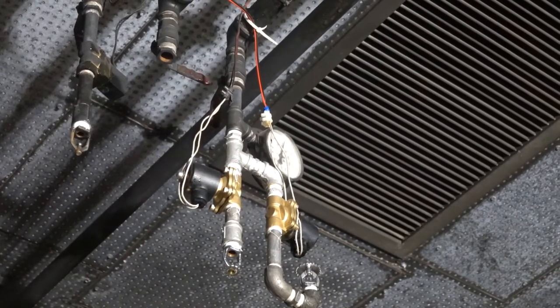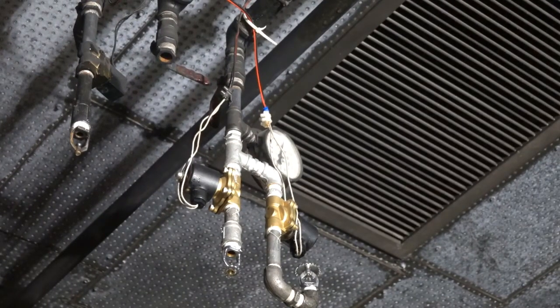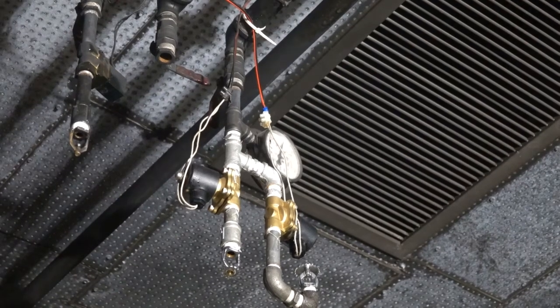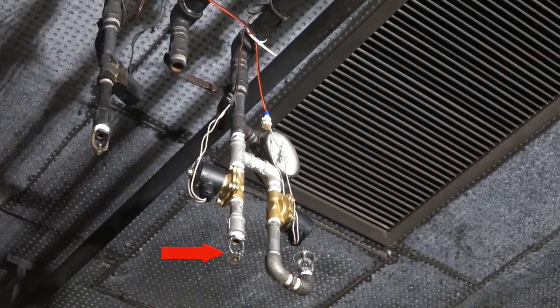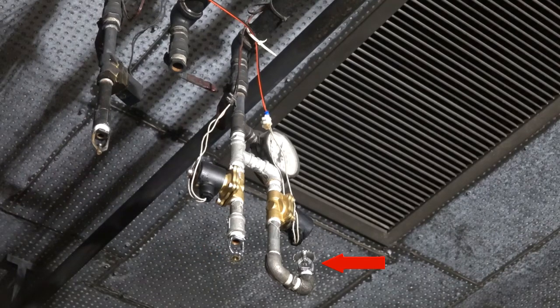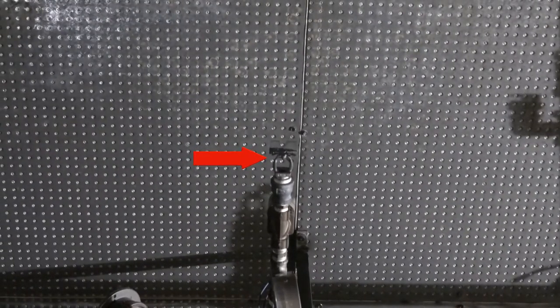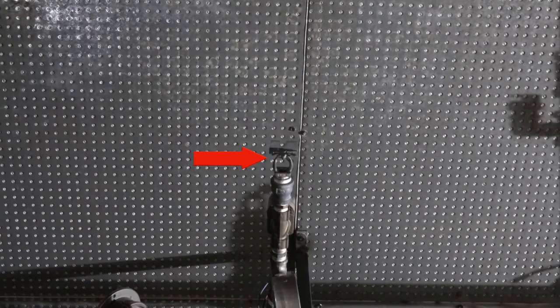What we have here is the 3 different types of sprinkler heads that we'll be looking at in this experiment. Let's look at them before we turn them on. You see the first one is the standard sprinkler. The one just beside it is the overhead or upright sprinkler. As you can see, they have no bulb installed because we want the water to flow as soon as we open them, we turn them on. And the last type of sprinkler head that we have is the sidewall sprinkler.